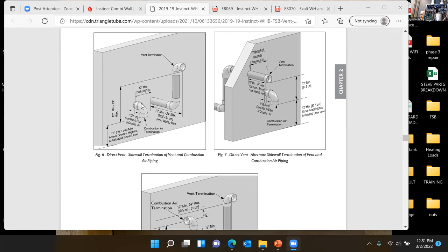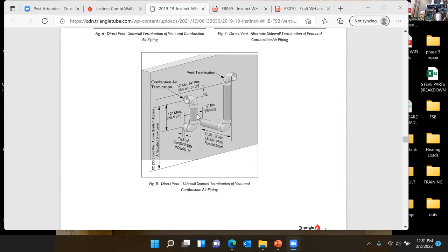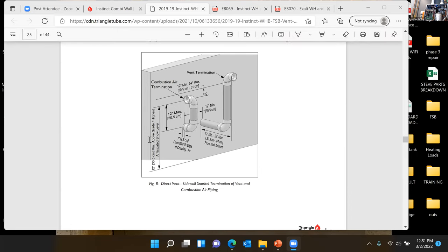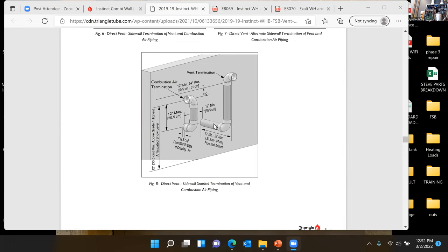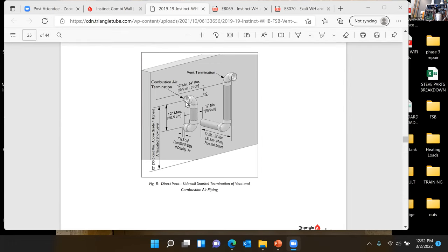Now, if you have to go up and snorkel up with your air intake, like this one, this install actually is not approved anymore. We have an engineering bulletin that's in the boxes with all the new boilers that shows it, but this is okay. We just need to put a small piece of pipe in here or a street 90 and 90 it down.